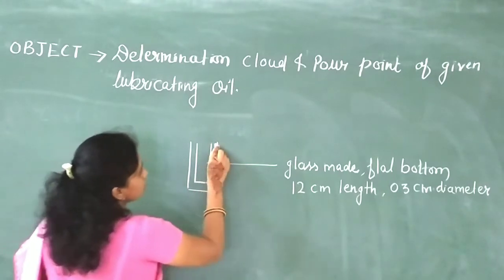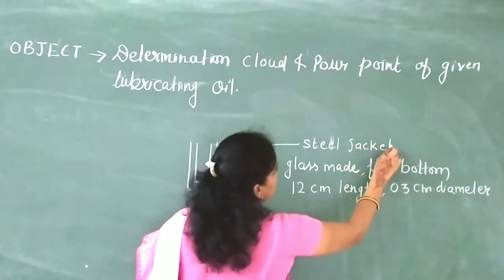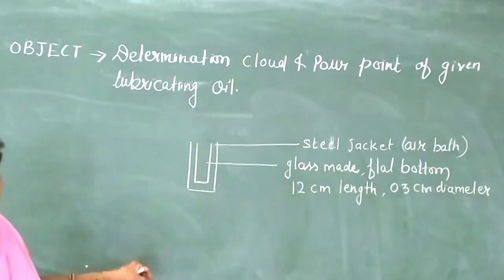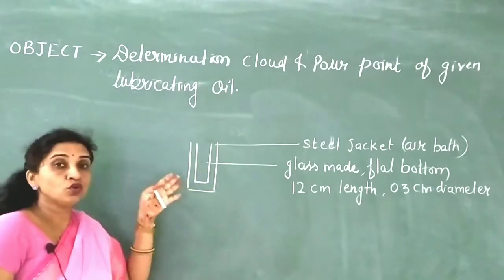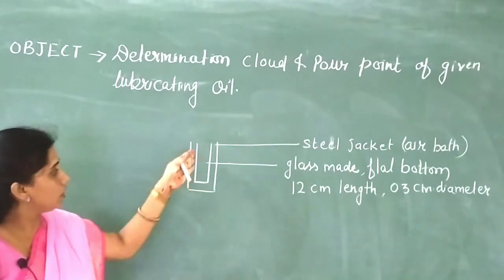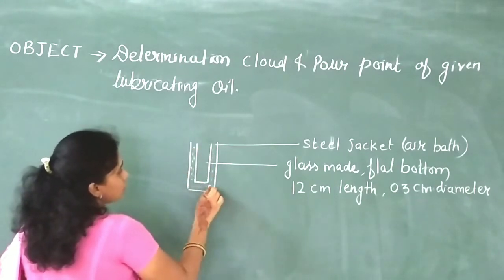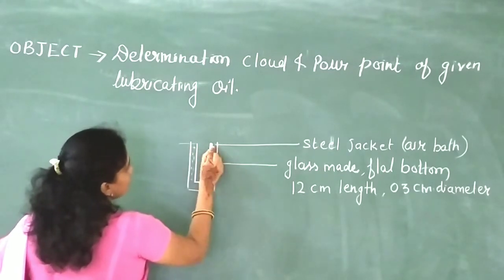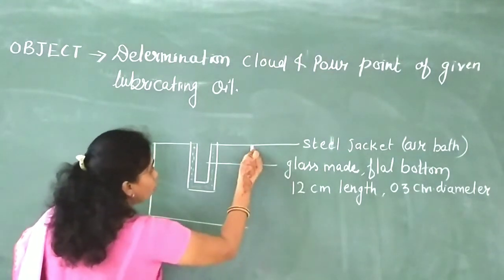The glass jar is inserted into a steel jacket. This steel jacket acts as an air bath — air is filled in the space of the steel jacket. Since air is a poor conductor of heat, when we want to cool the oil, we can maintain a very slow cooling speed using this steel jacket.